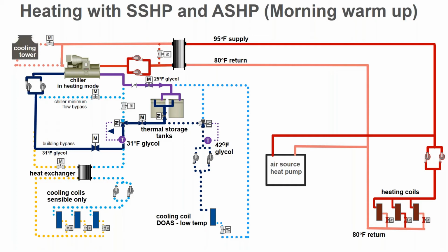The reason these things are very popular in the center of the country is because it's a more mild climate. When you get up to our area, you've got 0 degrees or -2 or 3 or 4, and these things become relatively inefficient. I don't know the exact numbers, but somewhere in a COP in a 2 or 2.5 range. So relatively low. But on those super cold days, you're going to need to get your energy from somewhere, and the air is the source in this case.